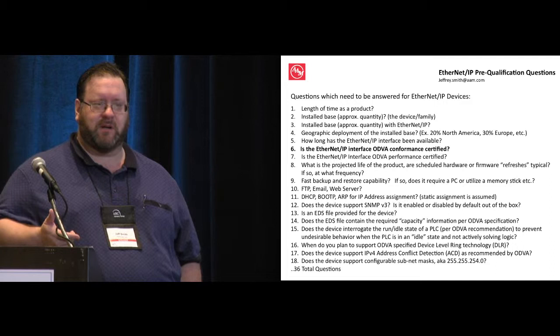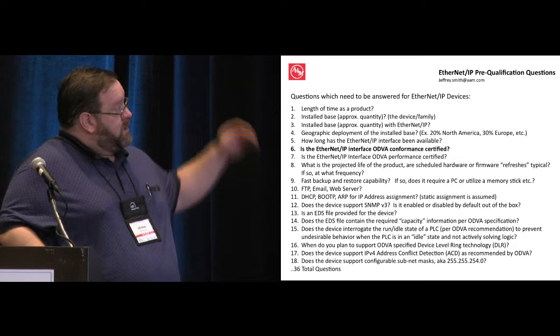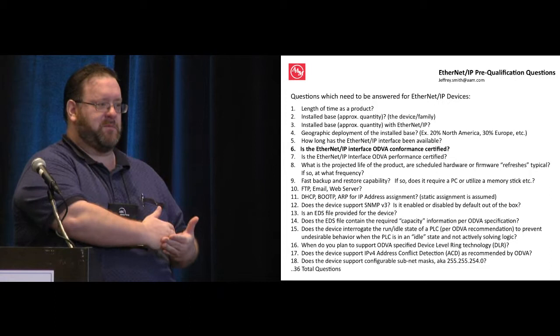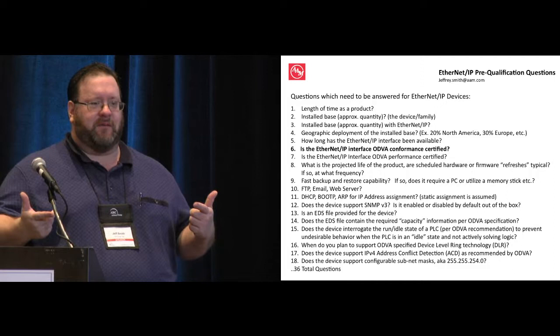I also participate, many may or may not know of USCAR. That's something that I myself and with USCAR, we're going to begin to push as a requirement for field devices. So once we get the questionnaire, we go through, do a battery of testings. We set established minimum requirements for packets per second. How does it recover? Does it meet this recommended ODVA practice? Does it meet this practice? Does it provide address conflict detection? There's just an entire list of things that we go through.